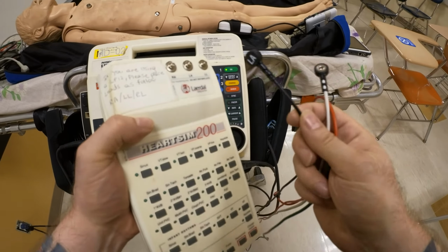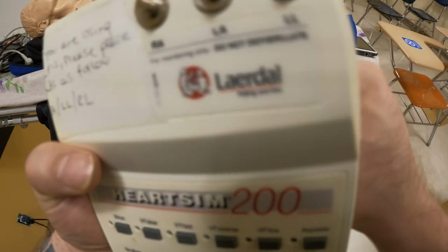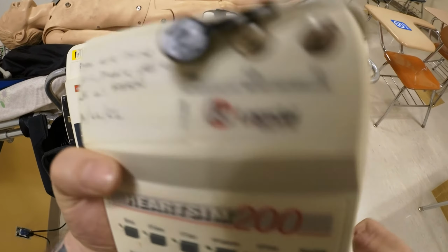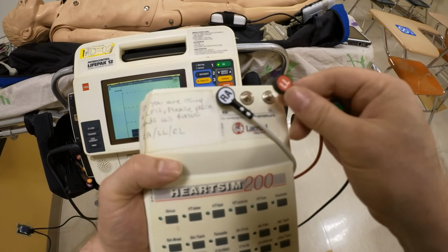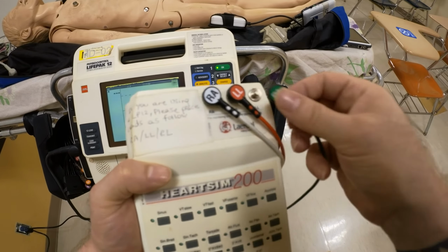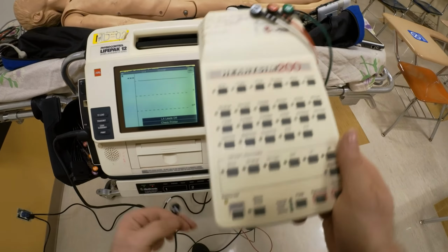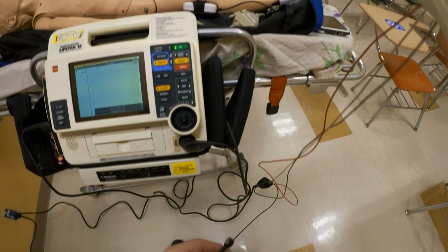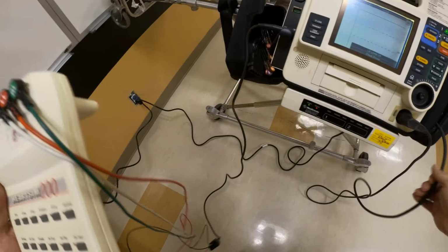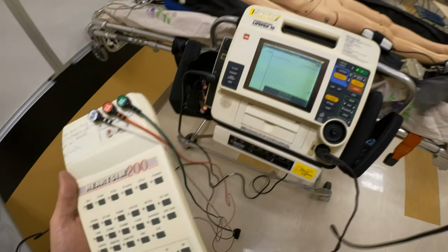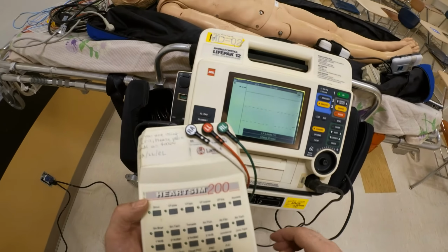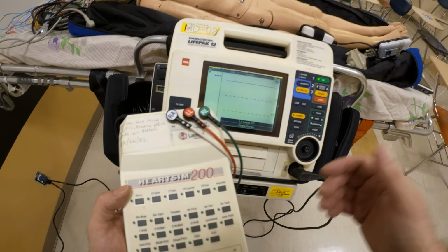So if you're a LifePak 12, right, first is going to be right arm. The next one is going to be left leg. And the last one will be right leg. So I'm specifically ignoring what's printed here for LifePak 12. This lead you do not need. The other thing you notice, right, there's no place on this device that I connect my pads to. So I cannot deliver electrical therapy with this device alone. I need to have something else, and I'll show you what you need.